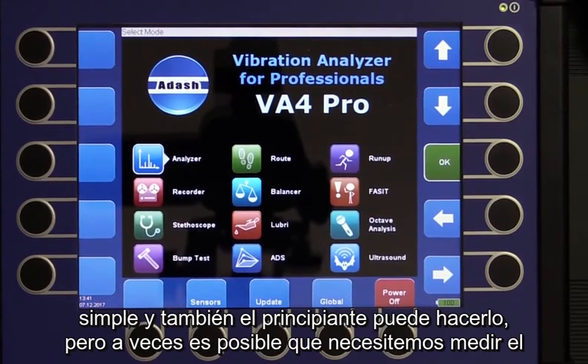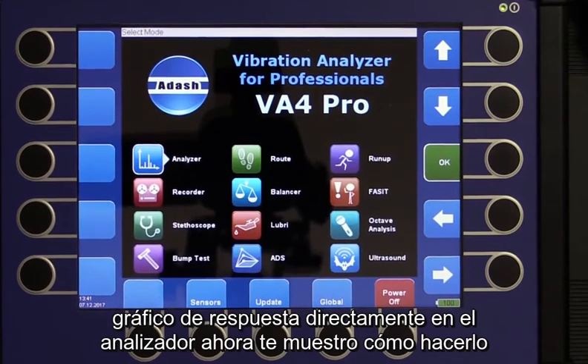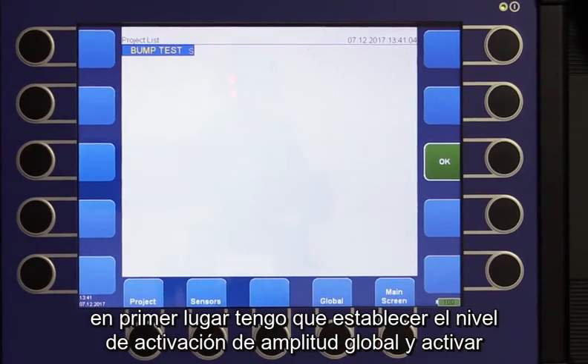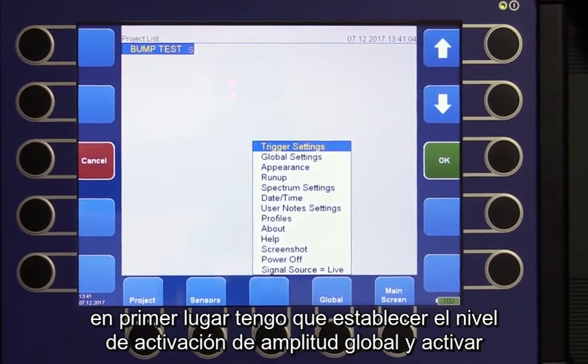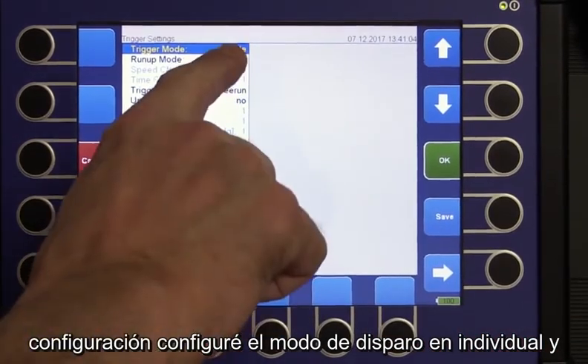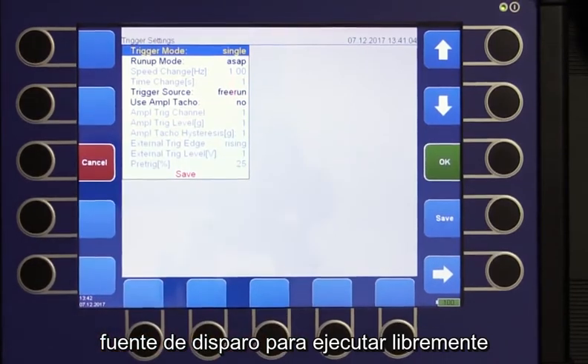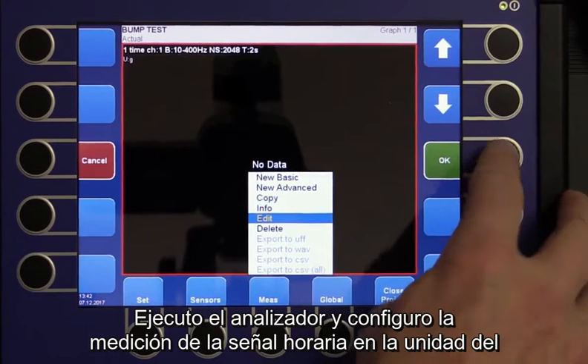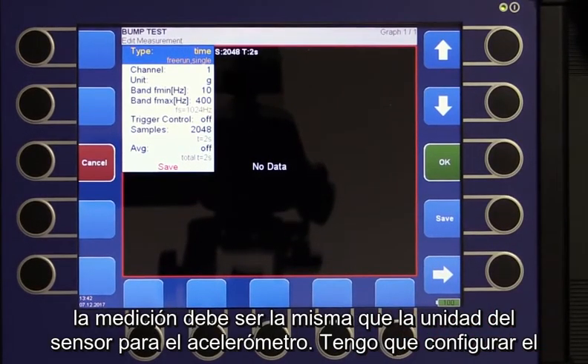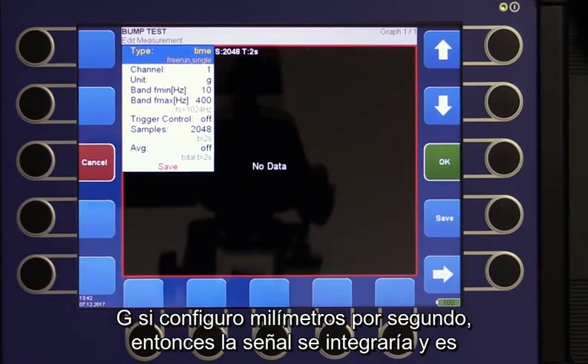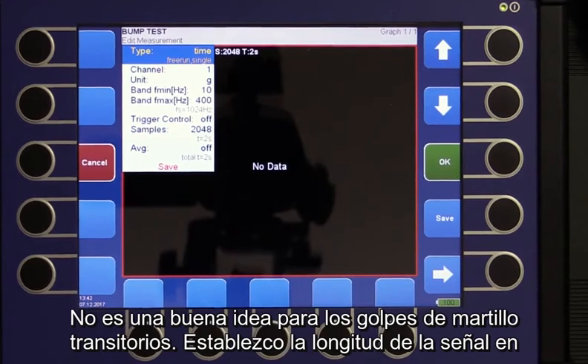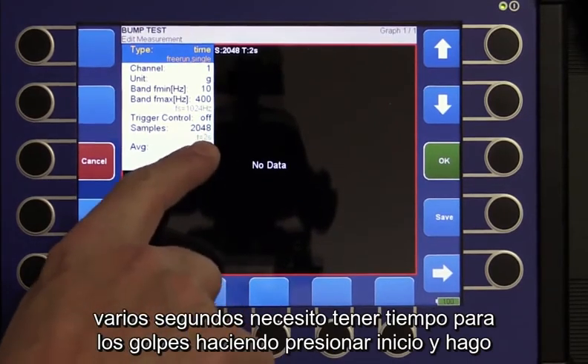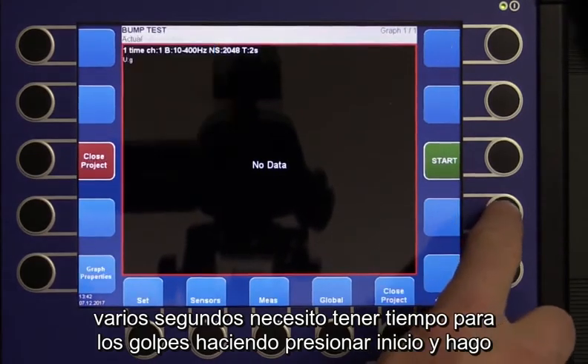Sometimes we may need to measure the response graph directly in the analyzer. First, I have to set the amplitude trigger level in the global and trigger settings. I set the trigger mode to Single and the trigger source to Free Run. I run the analyzer and set the time signal measurement. The unit of measurement must be the same as the sensor unit — for an accelerometer I have to set it to G. If I set millimeters per second, the signal would be integrated, which is not a good idea for transient hammer hits. I set the signal length to several seconds to have enough time for making hits, then press Start and make several hits.